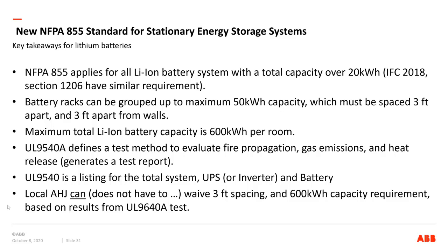What they get out of that is a test report, which should say that the battery solution doesn't propagate and states very low gas emissions and very low heat if there's a fault. ABB does offer lithium-ion batteries, and they have been tested to 9540A. We can support that or submit that report. And 9540 is actually a UL listing, for a total system. There's a lot of confusion about this, and the market is not quite sure how it's going to handle it right now.